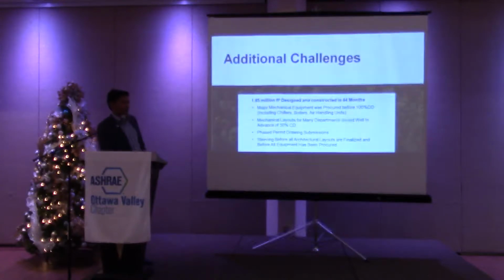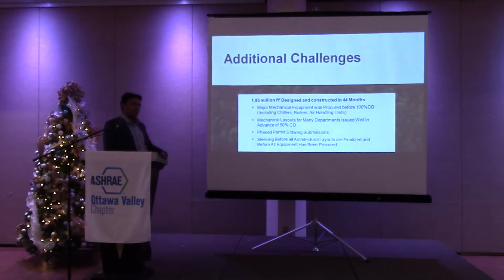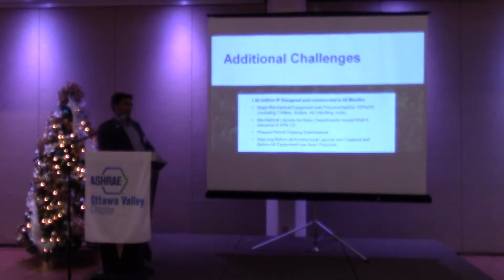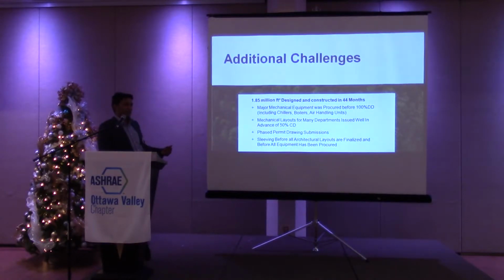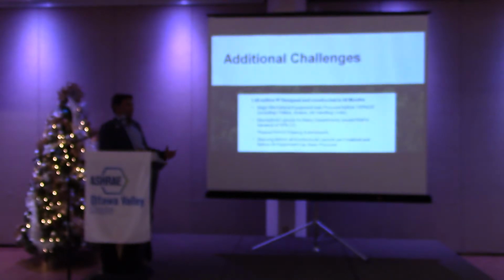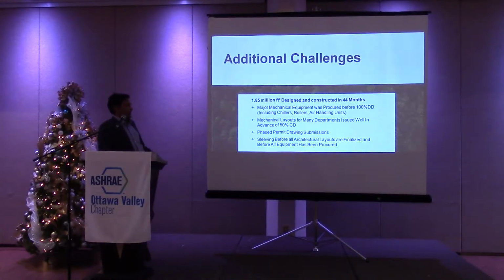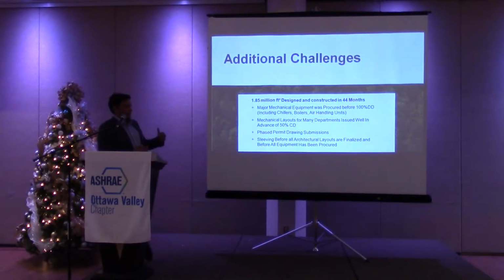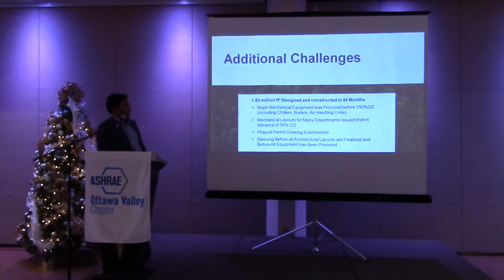Even working with the building department was interesting, because typically for new hospitals, they expect you to show up with a set of drawings, entire hospital design, so they can pick it apart and make sure it meets code. So in this case, we had to convince them that we would give them a core and shell of a complicated healthcare facility, and then we would come in and show them detailed layouts of ORs and inpatient towers and the dialysis unit, and that they would accept that that would be the approach we would take. And so it took some convincing, and we had a staged permit approach.